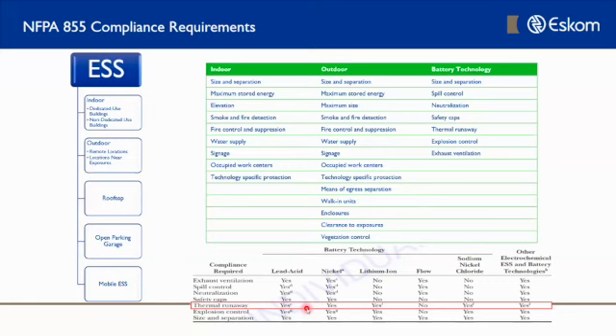There is still a possibility for thermal runaway whether you have lead acid, nickel, or lithium ion - lithium ion is the worst, and the point at which thermal runaway starts is the quickest. But the principle is it's not dependent or specific only to a particular battery chemistry, and we need to consider specific things depending on the actual chemistry of battery we're using. We can't just switch and swap things out, suddenly use another product, and not consider those factors when using a different technology type or component.